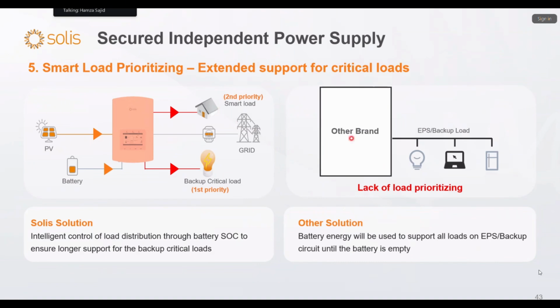Okay. In other brands, they only have one backup port, which is turned on when the grid is turned off, when grid outages happen. So the whole load drains the battery in a fast way, and you don't have any specific power available for the critical load. In this case, the battery will be drained faster because all the load will keep running until the battery is turned off. So in this case, you are monitoring the battery SOC, and it will turn off the load once it reaches a certain limit. So the customer can enjoy the rest of the power for their most critical loads.